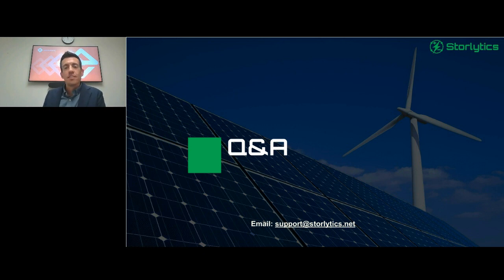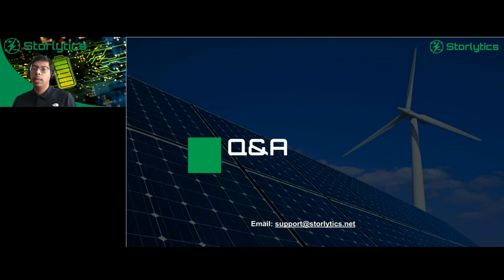Thanks, Chad. I was going to start with the same, but just quickly: the total running cost has two components. One is to maintain the state of health guarantee, maintaining 100 megawatt hour plus throughout the project life — maintaining that guarantee has a cost. The other part is the energy loss cost. Basically, you charge the system with a certain amount of energy and then discharge it, but because of losses, you don't get the same amount of energy out. The difference between the charge energy and discharge energy is accounted over the project life, and that's the energy loss cost.